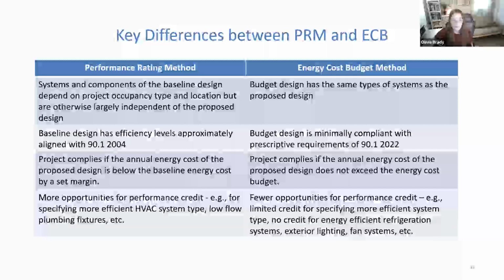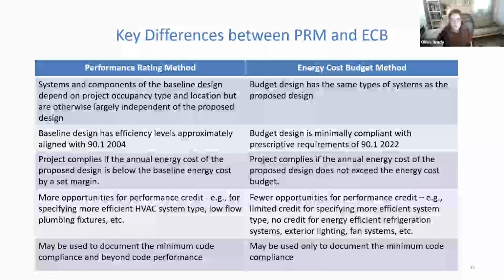Another important difference is that with the performance rating method, there are more opportunities for performance credit. So for example, projects can get credit for specifying a more efficient HVAC system type, low flow plumbing fixtures, and so forth. But with the energy cost budget method, the opportunities for performance credit or trade-off opportunities are more limited. So for example, there's no credit for energy efficient refrigeration systems, no credit for exterior lighting systems or fan system performance and so forth. And then the last very important difference that I want to mention is that the performance rating method may be used for documenting both minimum code compliance and beyond code performance, whereas the energy cost budget method may be used only to document minimum code compliance.